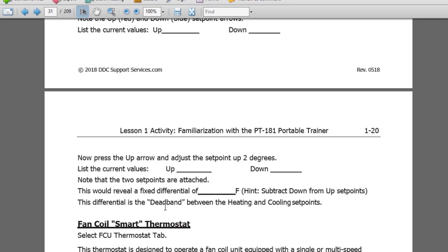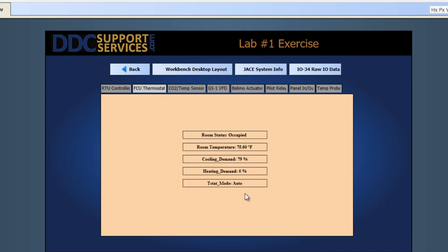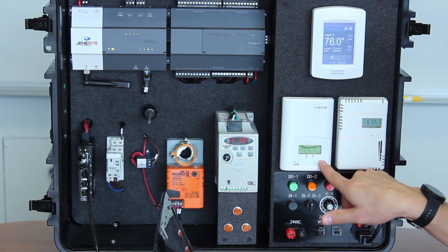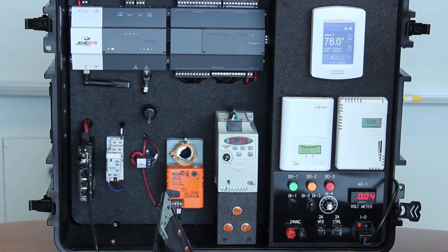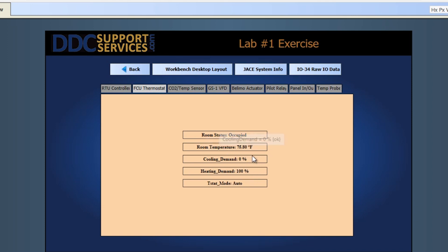In the fan coil unit thermostat you can see the statuses and set points. Right now we're showing a room temperature of 75.5°F. If we bring this up to 80 degrees, the heating demand should go up inside the JACE controller — and there it goes, heat demand changed to 100. It takes about 30 seconds to a minute. Similarly, if we change the cooling set point down and wait, the cooling demand would jump up to 100% or whatever percentage is needed to reach the target temperature.